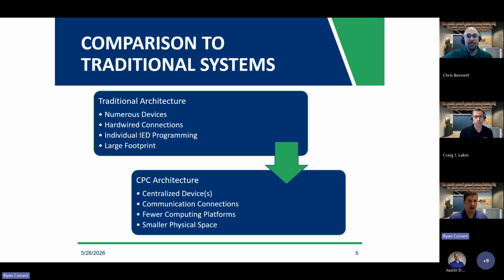If we want to compare and contrast CPC with a traditional architecture, the one we're more familiar with would have a lot of relays, hardwired CT, PT, as well as status and control points. There's going to be more copper cabling and more individual device programming. Obviously all these devices need to be housed somewhere, and that's typically within the control enclosure. That amount of equipment takes up a lot of space within a control enclosure, and it's typically the biggest driving factor of the size of the control house.